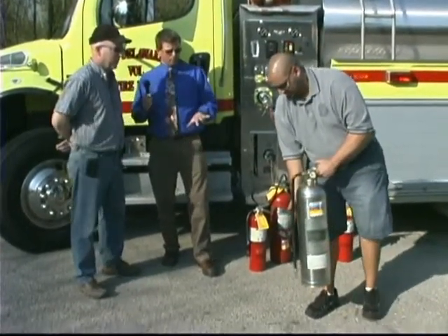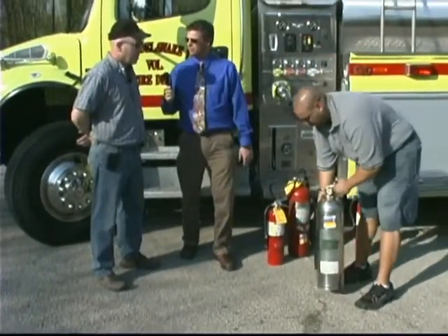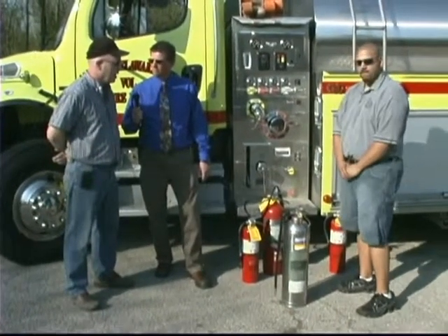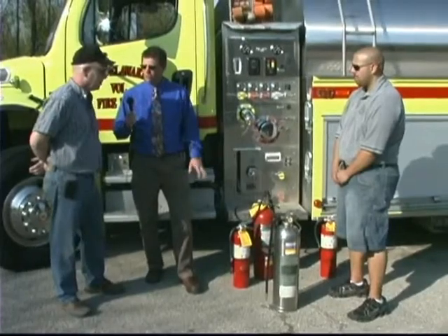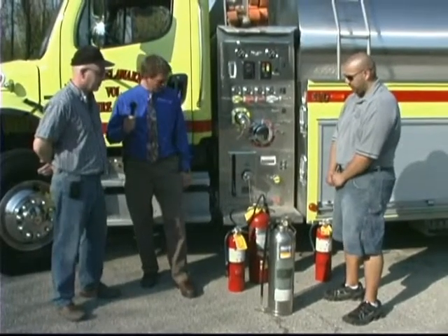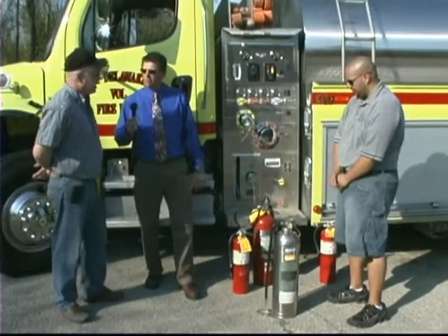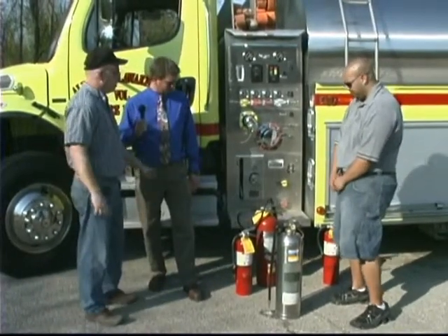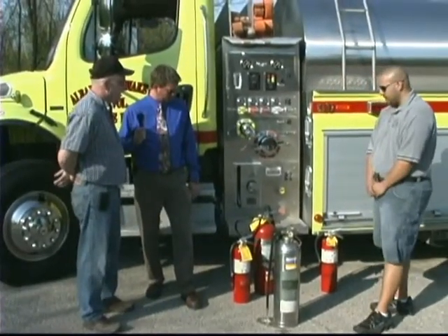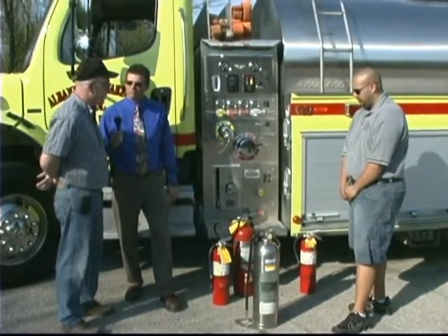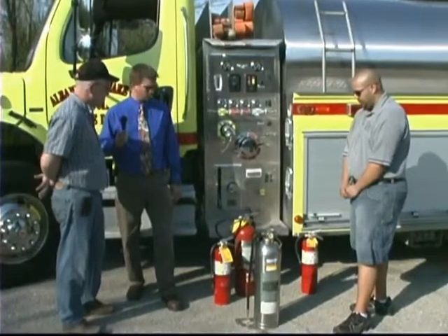So pressurized water, is that refillable? Correct. And it's just water refilled, and you can use an air compressor to recharge that. So you can just keep using that one over and over again. Correct. Okay. And how about your ABC type and your CO2 type fire extinguishers? Yes, both these types are refillable. With a gauge on them, you can tell by the gauge. It's very important if you have a fire extinguisher to check the gauge and make sure it is in the green, where it is properly supposed to be.